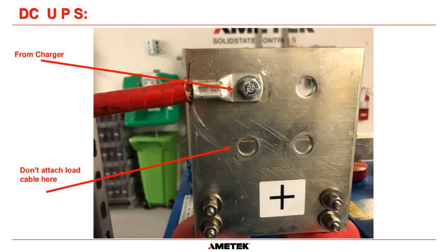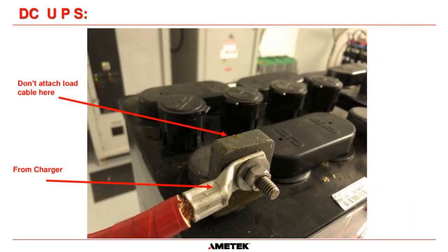And there's another example here on a smaller battery where a lot of people will put the cable on this side here. They will have their lug going on that side, and the bolt will go through there. And once again, the 2 cables are in parallel. It will work absolutely fine, but you cannot remove the battery for service without taking a load outage. So not a great design, and there's ways that you can get around it.